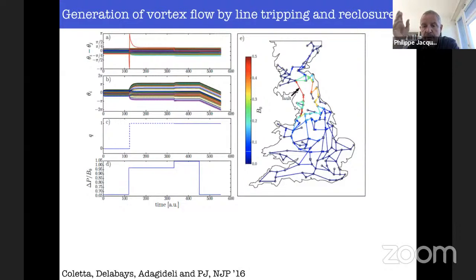Suppose you have a fault for some reason, and the line with the fault is indicated on the right-hand side by this arrow. Now you cut that line, you open it, and the power that was initially flowing, say from south to north through that line, has to be diverted to the other side of the loop.